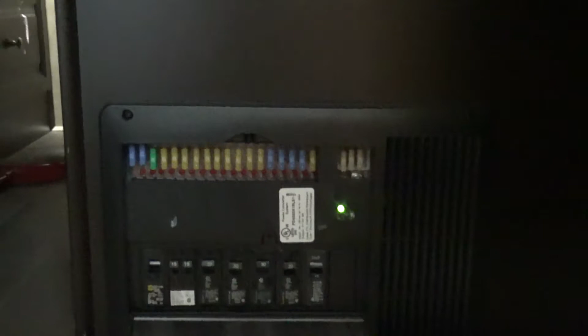So on mine, the AC output of the inverter was hooked up to the input of that converter. We were having the power coming out of the batteries when boondocking into the inverter being converted to AC. Every time you convert AC to DC or DC to AC, you get a loss of inefficiency. So the power out of the batteries going to the inverter was directly connected to this converter. This converter was changing it back to DC and charging the batteries, which the batteries were removing that DC, going to the inverter - so you had a loop going on.